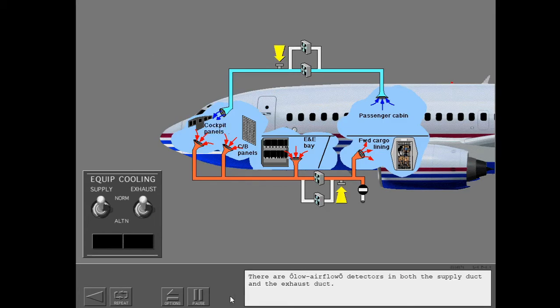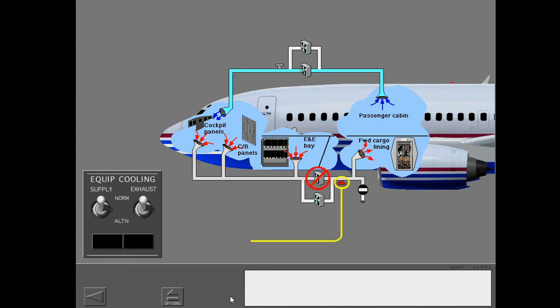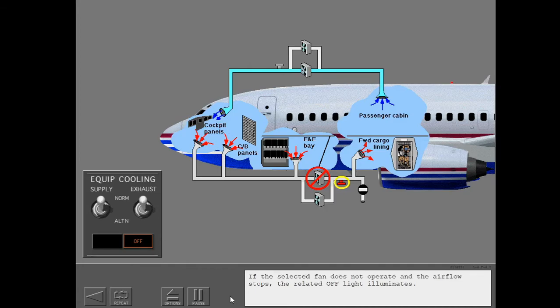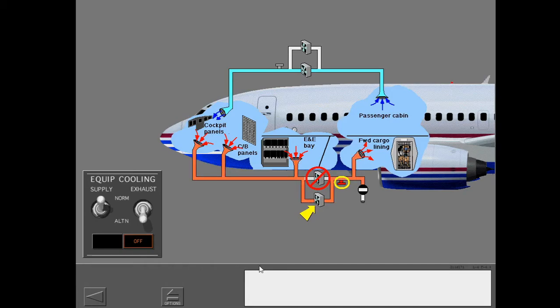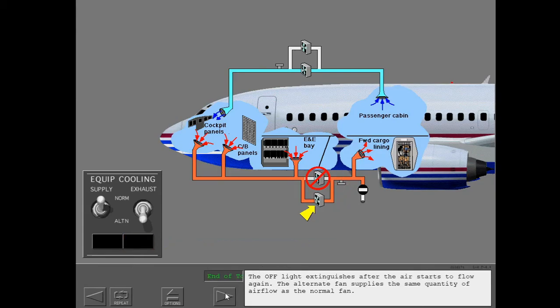There are low airflow detectors in both the supply duct and exhaust duct. If the selected fan does not operate and the airflow stops, the related off light illuminates. When the off light illuminates, you select the related alternate fan. The off light extinguishes after the air starts to flow again, and the alternate fan supplies the same quantity of airflow as the normal fan.